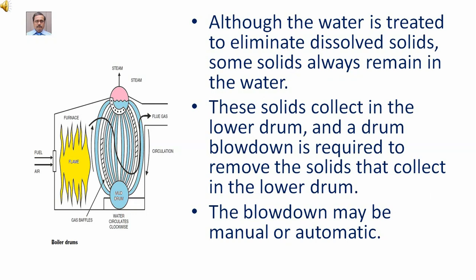Although the water is treated to eliminate dissolved solids, some solids always remain in the water. These solids collect in the lower drum and a drum blowdown is required to remove the solids that collect in the lower drum. The blowdown may be manual or automatic.